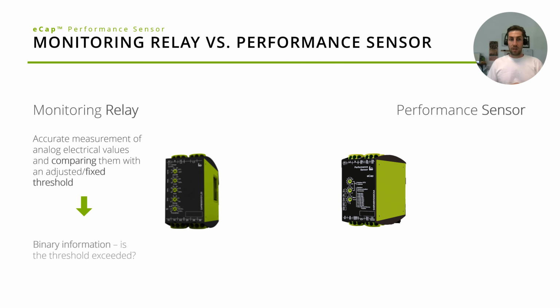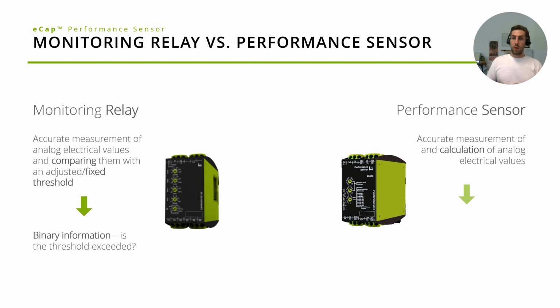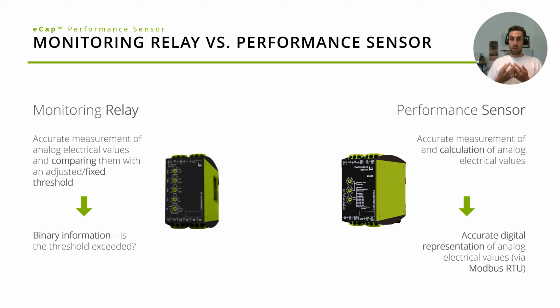The new thing compared to a standard monitoring relay is that instead of giving you like a relay output that says yes, this threshold was exceeded or not, we now actually have the chance to give you an accurate representation of that value that we're reading in, and then we're passing on that value through the integrated Modbus RTU interface.